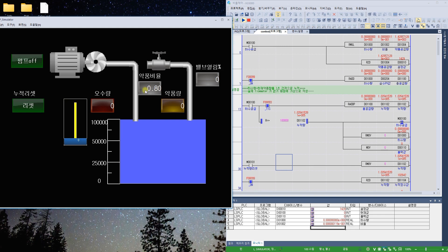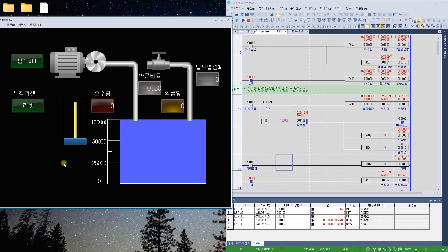For parts that require precise measurement, rather than inputting in real-time like this, a load cell is used to match the weight quantitatively. For example, if you put in 10,000 liters of wastewater, and you want to add 1,000 liters of chemicals, you first fill the wastewater to 10,000 liters, then measure and inject 1,000 liters of chemicals, and run a mixer inside to blend them. This increases precision and mixes the chemicals well to produce the desired result. For wastewater and sewage treatment, chemicals don't need to be dosed that precisely, so this method is also used.